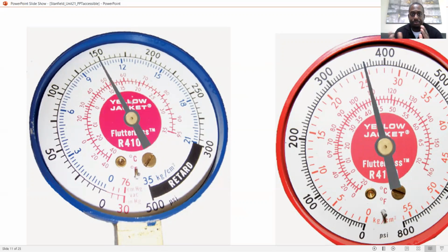Again, with digital gauges, all you have to do is select what refrigerant you're working with, and it's going to convert the saturation temperatures to the correct table. So it doesn't matter what kind of system you're working on, you can get the correct saturation temperature. As long as you make sure you set the gauges, there's a refrigerant button. You just hit the button and switch it to whatever refrigerant you're working on, and these numbers will magically change to reflect the correct refrigerant table.